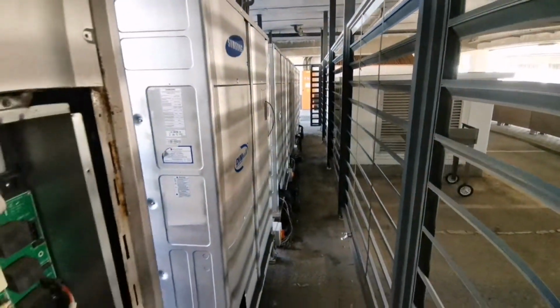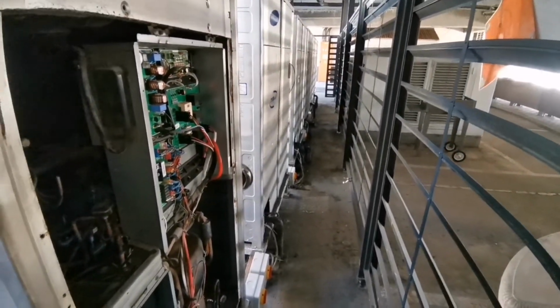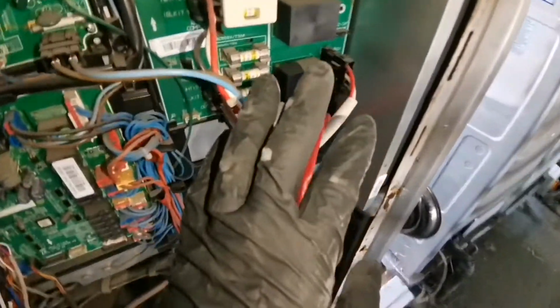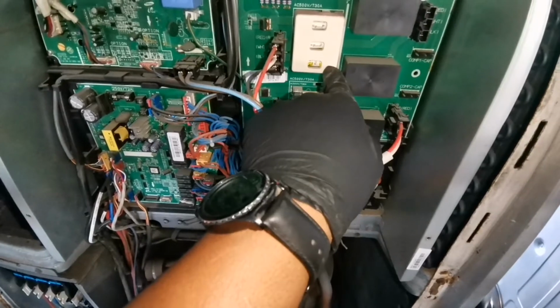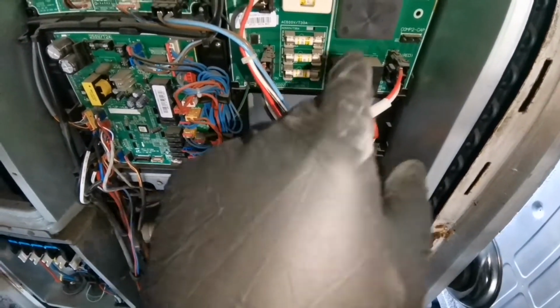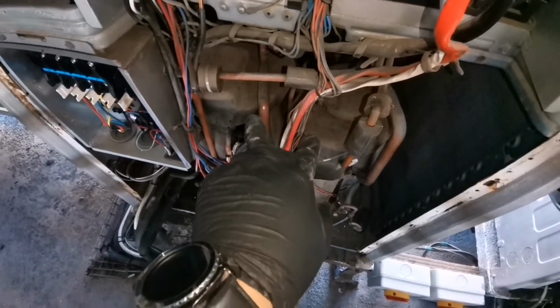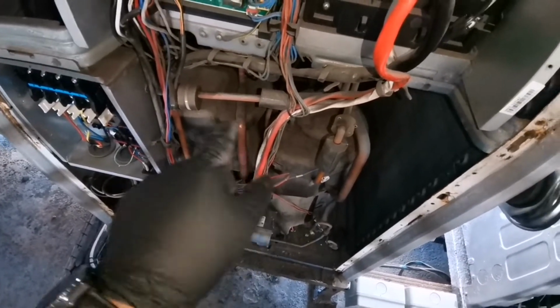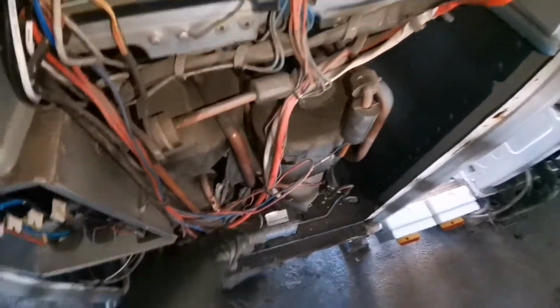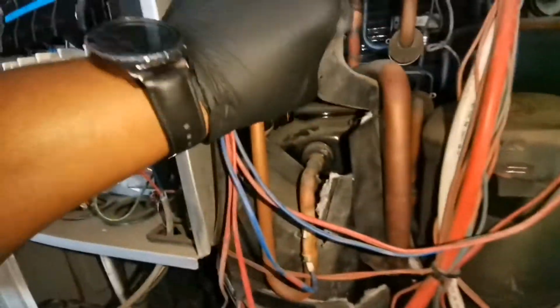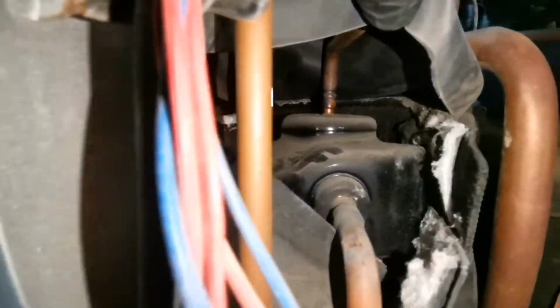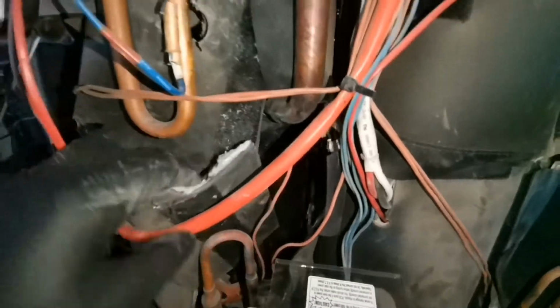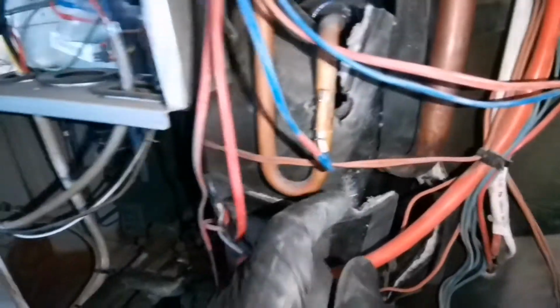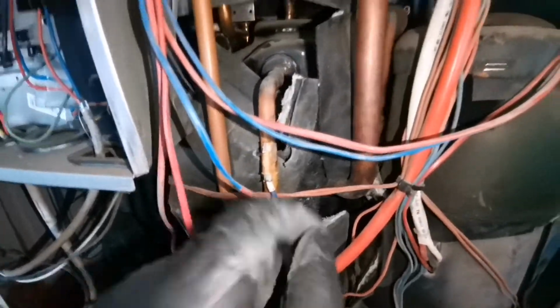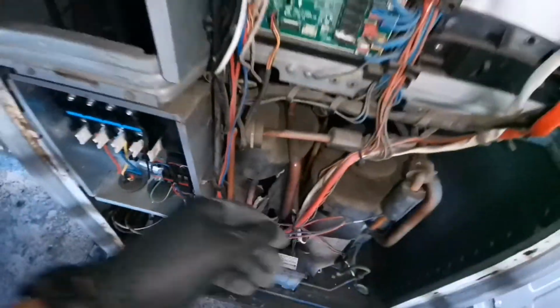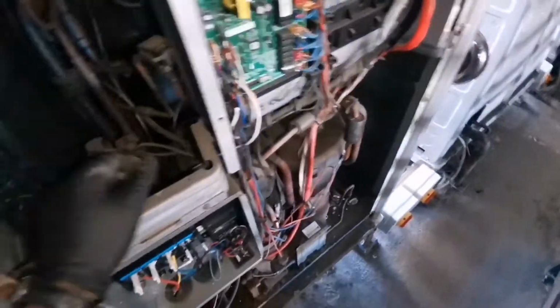So here is our VRF system, and on this one I pretty much have all the information I need. We're going to have to replace all these fuses. Depending on the oil, we might end up changing both of these compressors. So like I said, these are digital scroll compressors, right? So if you hear that, that is a load on, load off. These are Copelands. I think this was the last Copeland compressor Samsung used. After that, they started manufacturing their own compressors, which are in the DVM+ system, which is a complete inverter setup.